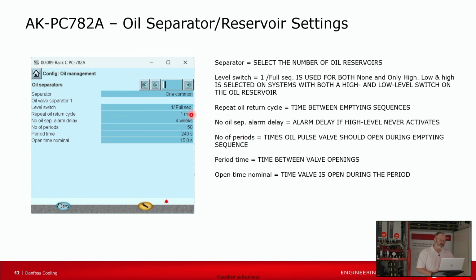So in this scenario, if you follow the little laser here, we're telling it when the high level switch activates, run through a full sequence. And that full sequence here, we've got a 1 minute repeat time, and then the period time is 4 minutes, 240 seconds, and then a nominal time of opening. What all of that adds up to is, when the high level switch is closed, I want to open the pulse valve. I want to open the valve for 15 seconds every 4 minutes, and then I'm going to wait 1 minute.